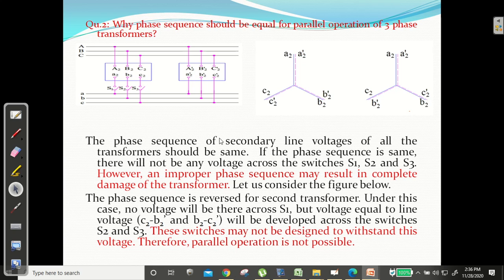The phase sequence of the secondary line voltage of all the transformers should be same. If the phase sequence is same, voltage will not come, it will remain zero, no problem. But if the phase sequence is not okay, then an improper phase sequence may result in complete damage of the transformer.